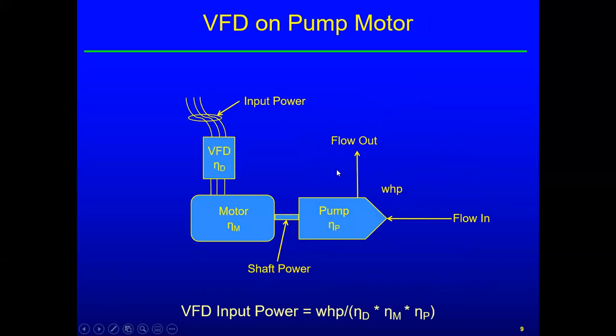Adding a VFD potentially adds another loss to the system. If it's operating at 60 hertz, you have the inefficiency of the drive with no benefit — you're actually going to use more energy instead of less. If you've got a VFD, you've got to have it modulated back off full speed to realize energy savings.